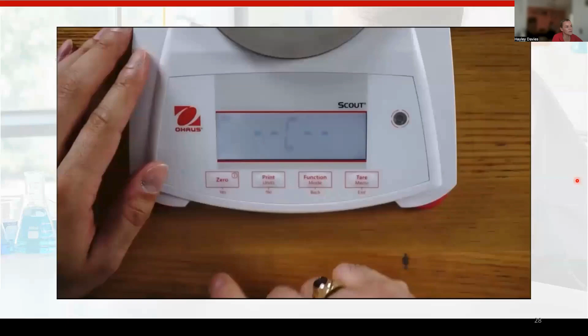And this is where he's going to do the calibration. You get to choose whether you want to do a span calibration or a linear one. The span calibration uses one calibration point, and the balance will know what calibration weight it needs. It's just flagged up 200 there. You pop the 200 calibration weight on, and it will readjust itself, and it's done. So that is how simple and quick it is to perform a span calibration on the Scout balance.